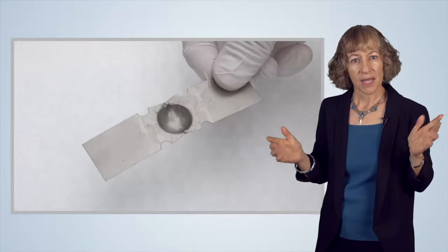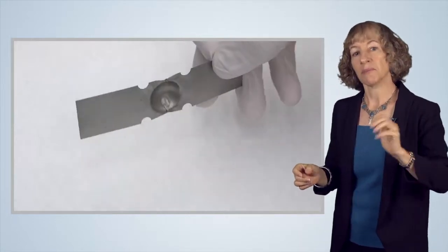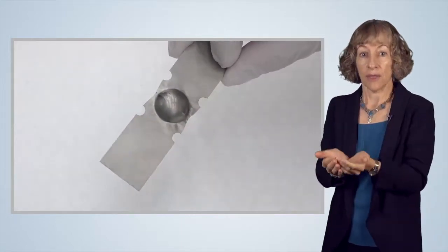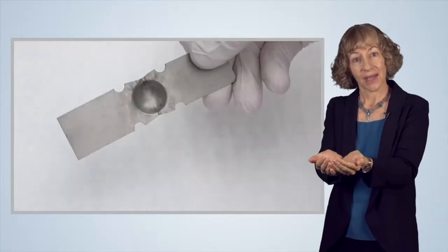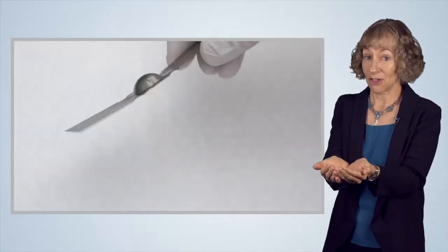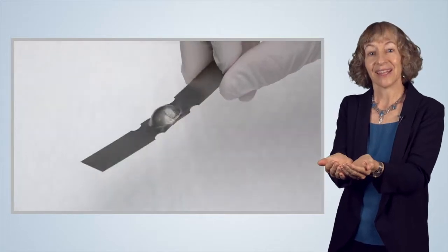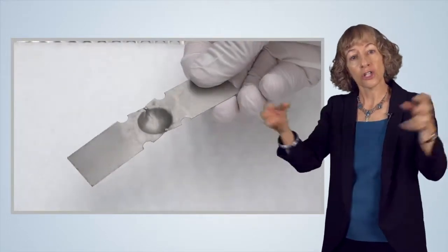Why tungsten? If we want to melt a metal, its container, the boat, must remain intact during heating. That is, it shouldn't melt along with the source. And we need to conduct a large amount of current through this boat as well. So we use tungsten boats because tungsten has a higher melting point than our source metals. And it's very electrically conductive, allowing resistive heating to occur.